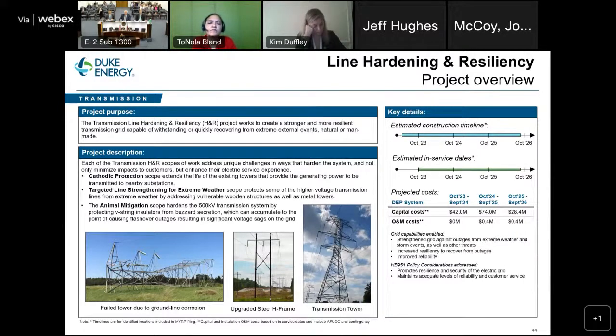For the targeted line strengthening for extreme weather scope, you can see a picture in the middle here. This is a typical H-frame design transmission structure. This is very common in our territory on the 230 kV and 115 kV systems. What we are doing is replacing vulnerable and aged wood poles and upgrading them with steel poles. When we replace a wood pole with a steel pole, we're designing that to the very latest standards. We heard about the NESC standards earlier. In a coastal area, for example, a new pole that's installed is designed up to 140-mile-an-hour wind scenarios. That's a great improvement over the traditional standards that were in effect when these poles were installed 50, 60, 70 years ago.